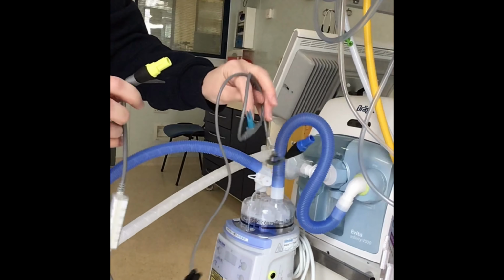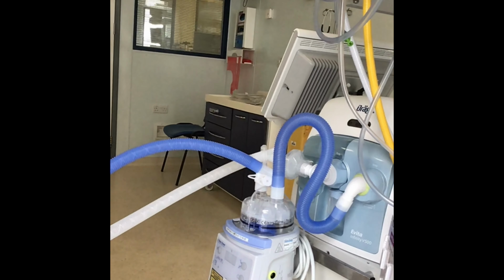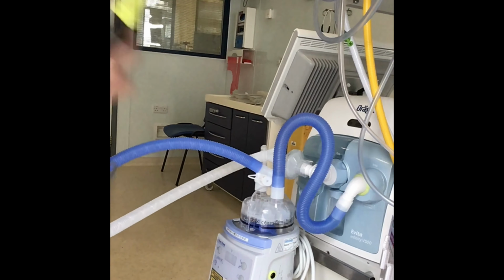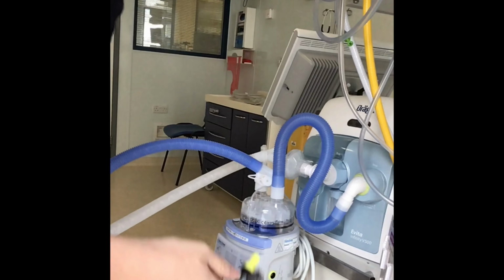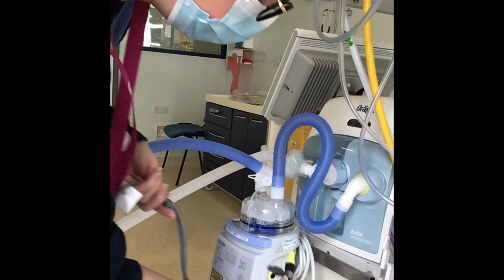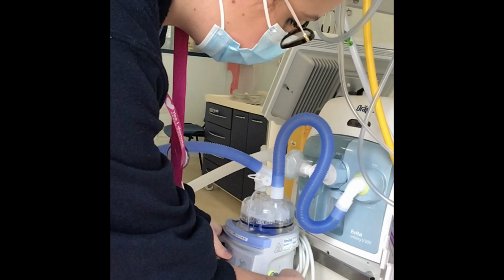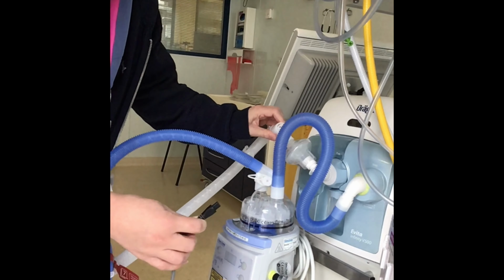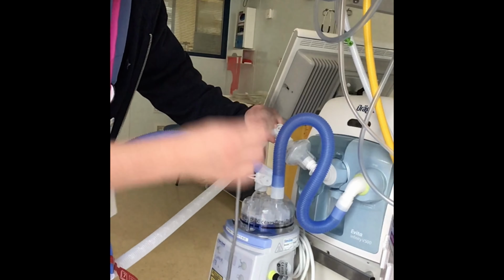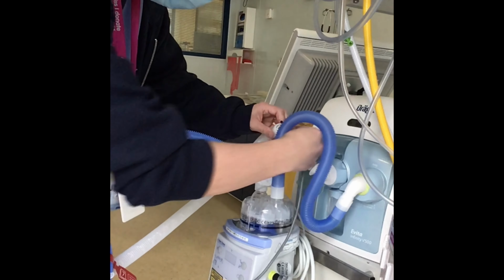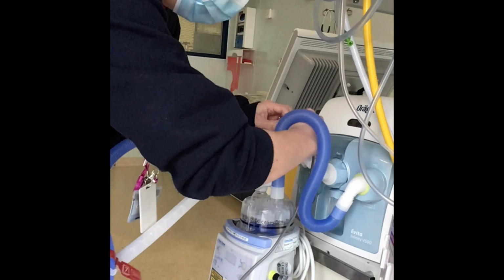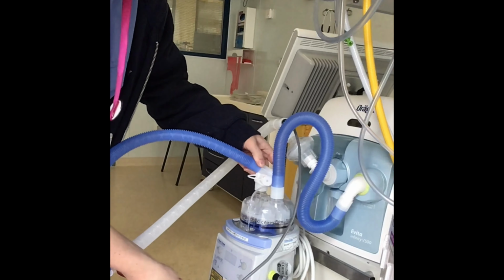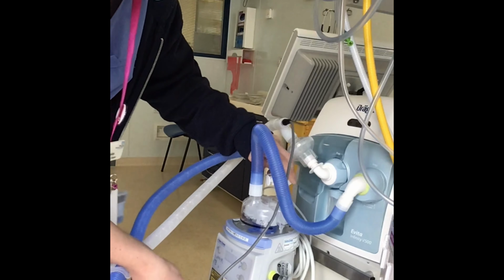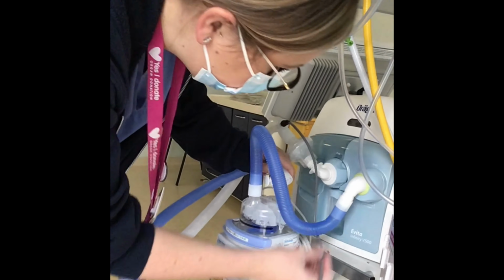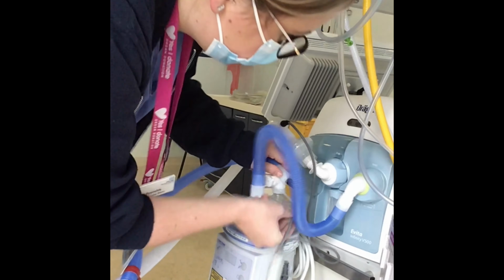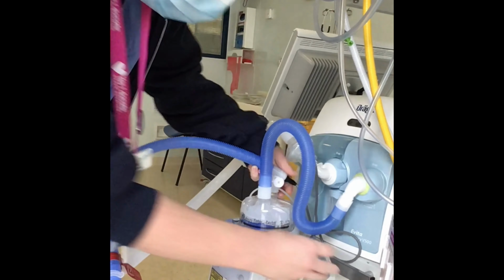They come in two pairs. Start with one and get it all into place before putting the other in. So you've got a yellow end here, and you can see you've got a yellow hub on your actual humidifier. Just push and you'll hear a click. On your white tubing you've got a 2-pin, and on this yellow part of the tubing you've also got a double pin, so that will just push into there. And then at the back of your blue you've got a 3-pin, and you've got a 3-pin here, so they will just line up and push in. So that's one cable done.